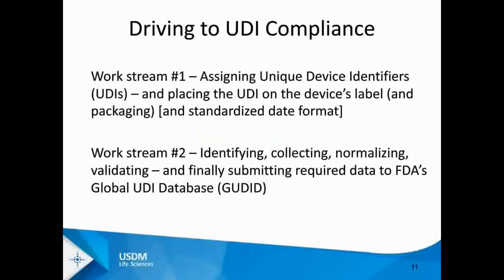There are two work streams when working with clients on UDI. The first is around assigning device identifiers to products, creating UDIs on product labels and higher levels of packaging, and dealing with the standardized date format.